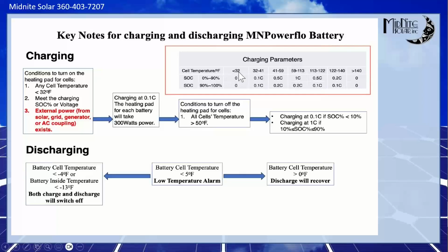But if the cell temperature is below 32, we turn the heaters on, but we do not start charging until we get to 32. And between 32 and 41 degrees Fahrenheit cell temperature, now this is internal in the battery, we charge at a 0.1 C. 41 to 59, it's 0.5 C, which is starting to get pretty stout. And then, like I said, in the window here, it's a full 1 C.